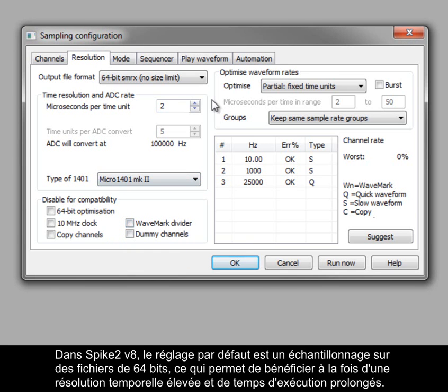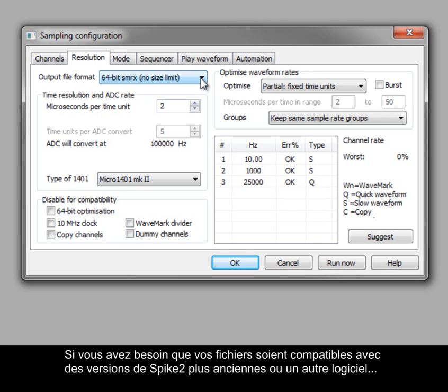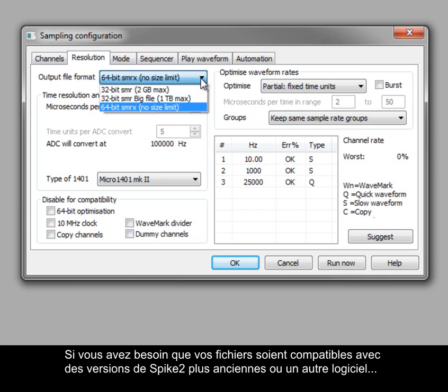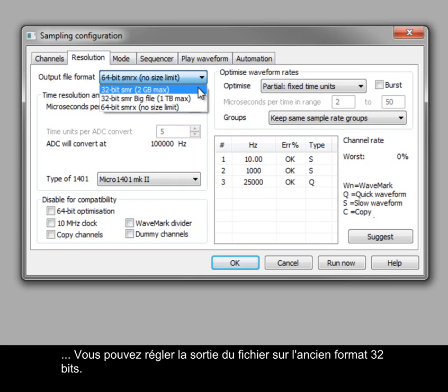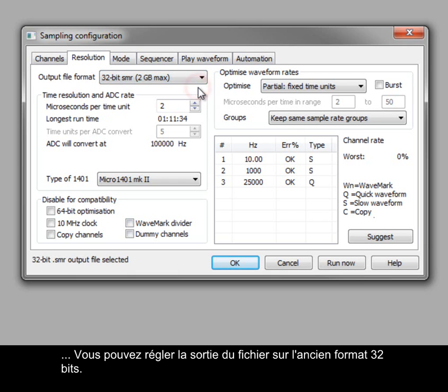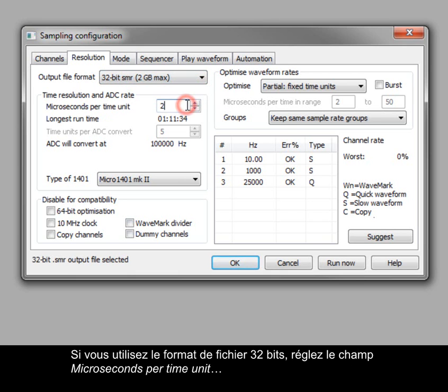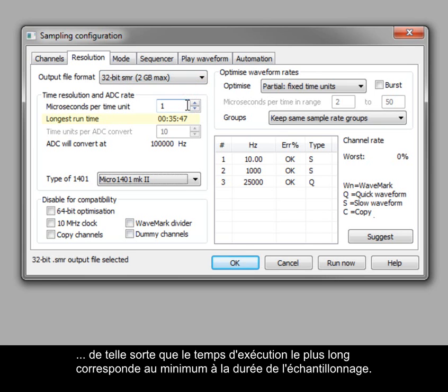In Spike2 version 8, the default setting is to sample to 64-bit data files, which allow both high timing resolution and long runtimes. If you need your files to be compatible with older versions of Spike2 or other third-party software, you can set the file output to the old 32-bit format. If using the 32-bit file format, set microseconds per time unit so that the longest runtime setting is at least as long as you want to sample for.